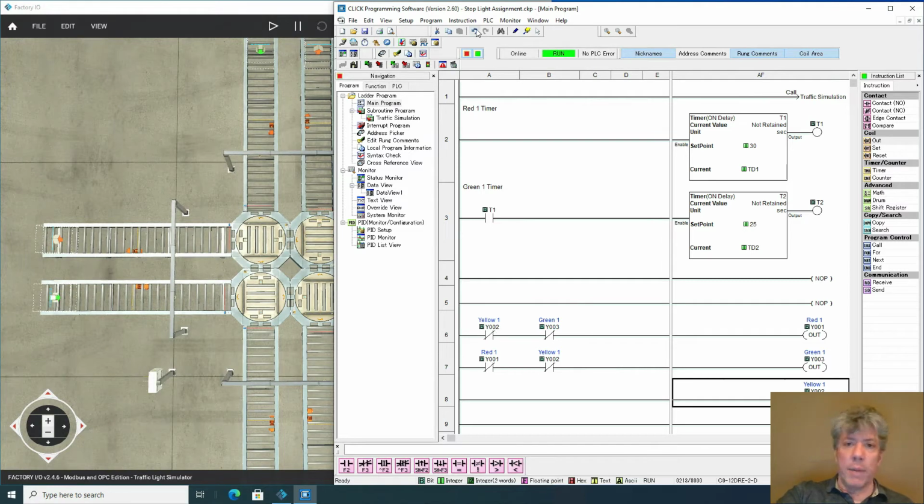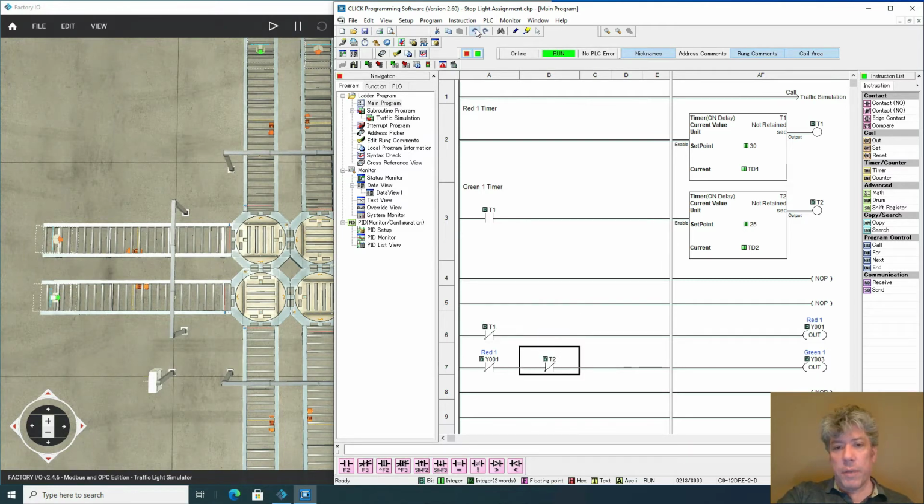So in fact, I'm going to make my life easy and go back to before I made such a big mistake. It's often a mistake to drive outputs based on the status of other outputs. You can end up with a circular reference. You remember Excel, when you were learning Excel and you typed a formula in one equation and depended on a variable in another cell, and that variable depended on the first equation? Well, Excel would always give you a circular reference warning. PLC programs or software won't give you that warning. They'll just do whatever they can to be consistent with the logic, which will not be what you want, I guarantee. So it's better to think through this and make sure it makes sense.